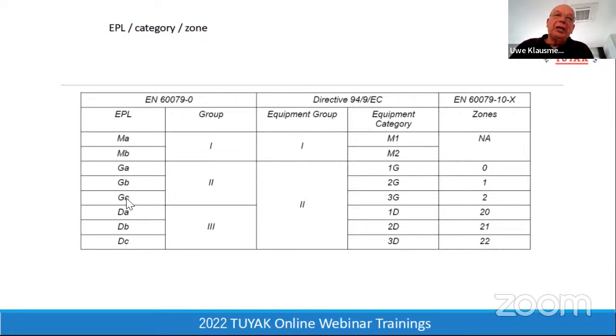It's so confusing, and it's always very hard for our experts in the field to follow this decoding system, going from the marking of the equipment to the necessary safety level you need. Because the only thing you know in the field is: I have zone 0, zone 1, zone 2 from the zone plan. In my zone plan, I can see these 3 classes of zones, or if it's a dust hazard, then zone 20, zone 21, and zone 22.